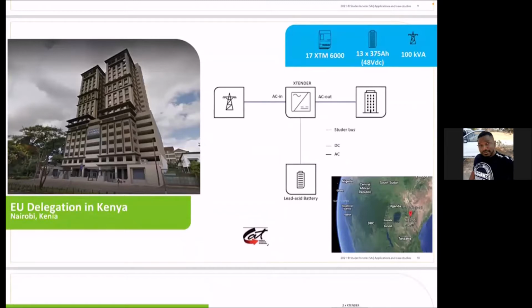One of our best projects was in Nairobi, Kenya, at the European Union delegation. This was quite a big system as well: 17 XTM 6000 charger inverters, 13 times 375 amp hour 48 volt battery bank, and also 100 kVA of grid power feeding in.